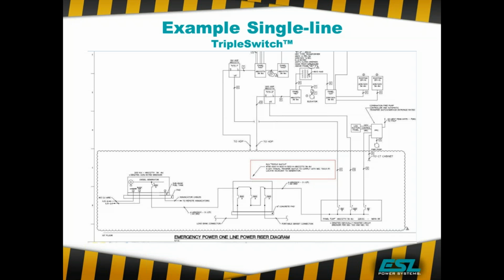So if this were an existing building, for instance, you wouldn't have to go back in and figure out, okay, where do I put a breaker to make sure this is interlocked? Where do I put a breaker to make sure that's interlocked? Does the generator have breakers? Where do I put the Kirk keys or the Kirk locks? You can just drop this in and tap into the existing conduit, and you're pretty much good to go. So from a design standpoint, very convenient.